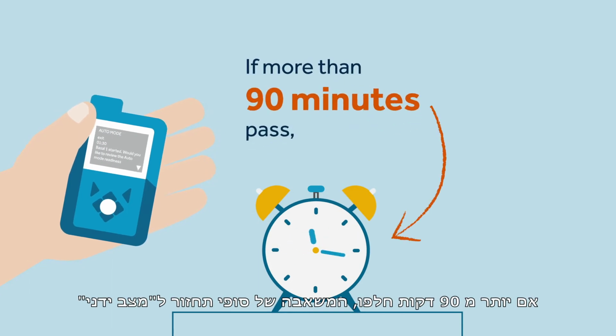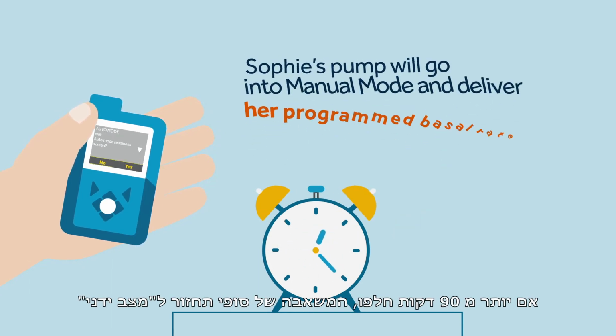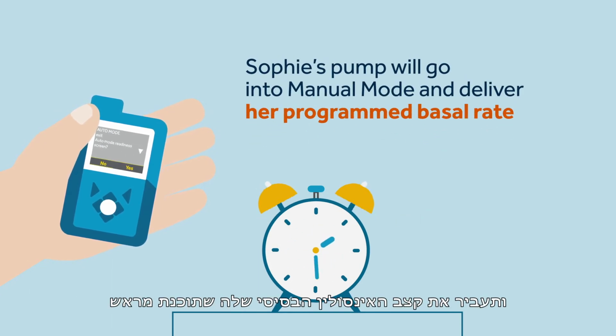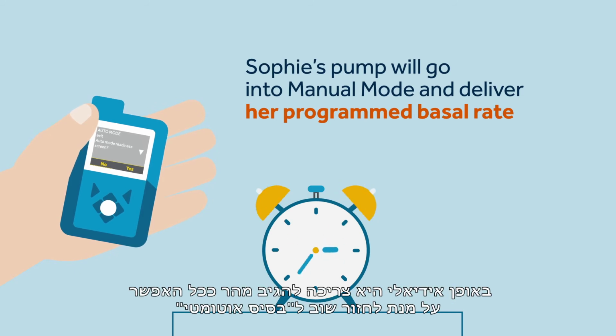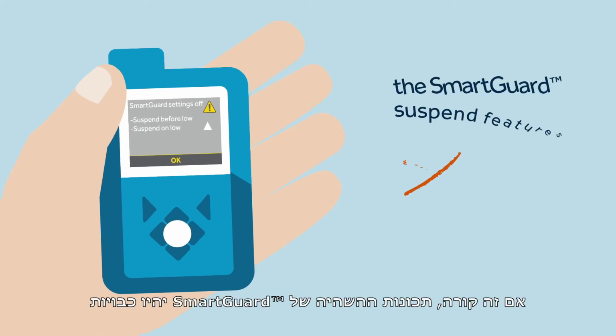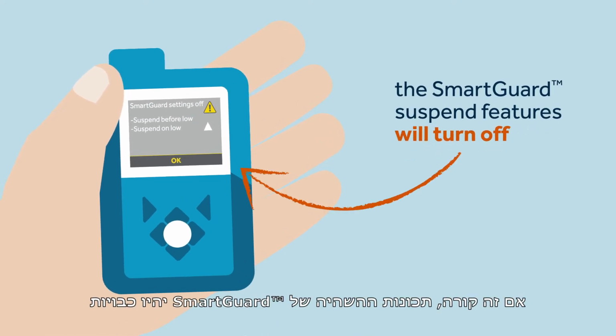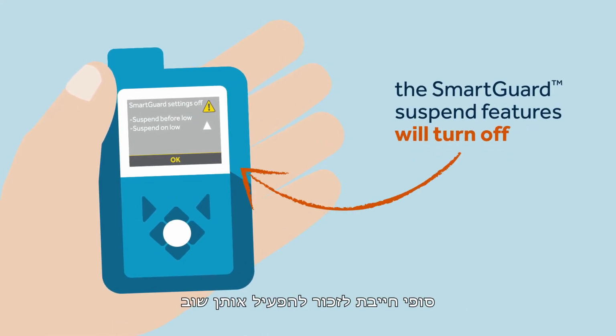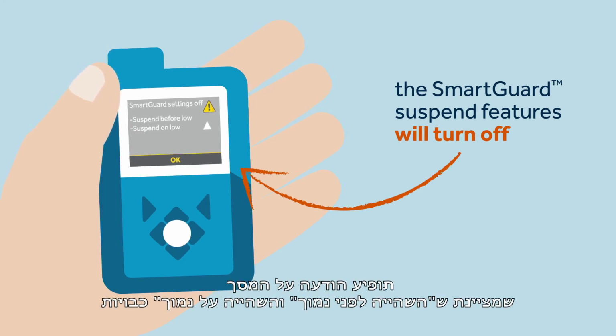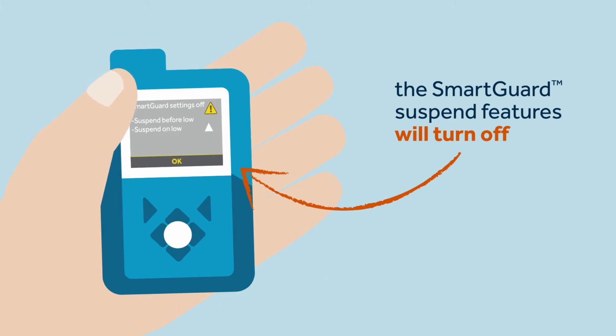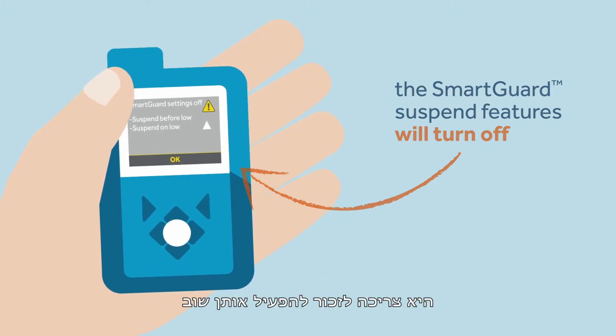If more than 90 minutes pass, Sophie's pump will go into manual mode and deliver her programmed basal rate. Ideally, she should react as fast as possible to return to auto basal again. If this happens, the SmartGuard suspend features will be turned off, and Sophie must remember to turn them back on. There will be a message on the pump stating that suspend before low and suspend on low is switched off. She needs to remember to switch them back on.